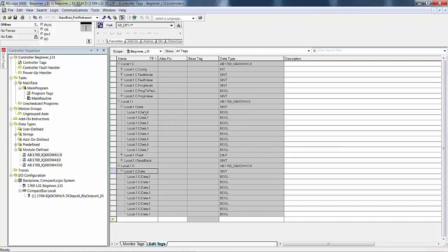The screw terminals on your I/O module, and in the manual we have a photo with callouts to clarify this. This location in memory, Local:1:I.Data.0, that bit in memory represents the state of the input field device that is connected to that screw terminal.